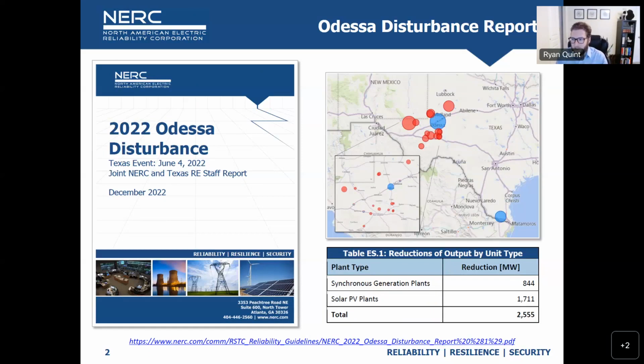We had a fault in that same general area. Multiple solar plants tripped or ceased power consumption or production for various reasons, and a number of synchronous generation facilities also tripped off in addition to the solar PV resources. So this event was bigger. This event was the biggest widespread solar loss event, resource loss event, we've seen in our endeavors to get a handle on the IBR topics. Solar amounting to about 1,700 megawatts and synchronous at about 800 megawatts.